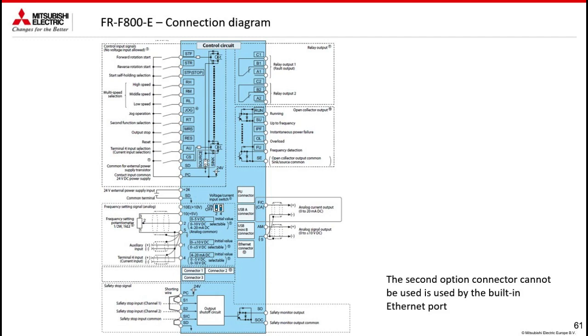Jog is used to perform jog operations, generally at 5 Hz, as long as the signal is kept high. Then RT is present for the second function section, for example a second motor, or in case you want to have second ramps. So when RT is active, it is like changing the recipe of parameters. However, it will be necessary to fill in the parameters of the second function. MRS is used to release the motor by inertia, but it is not a safety.